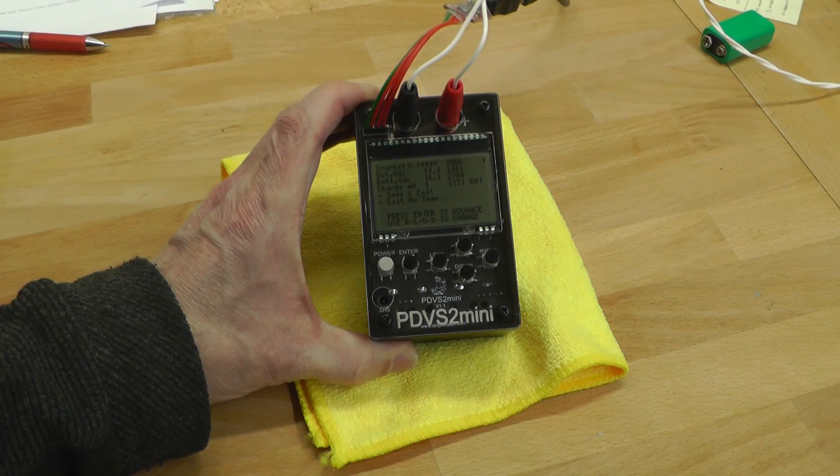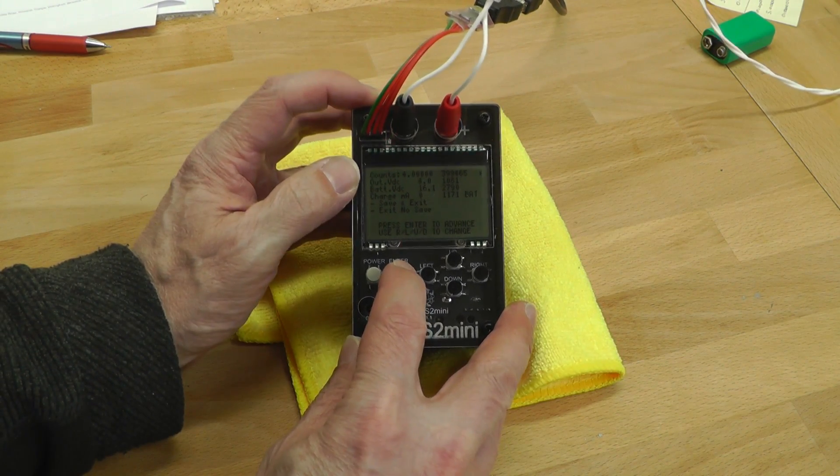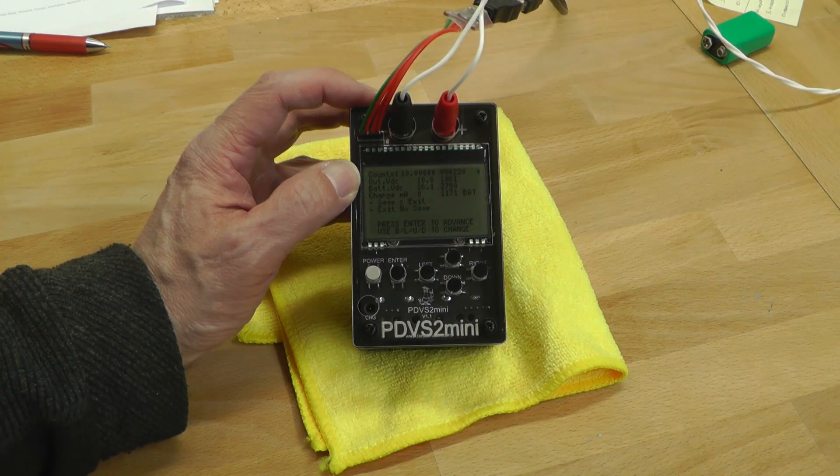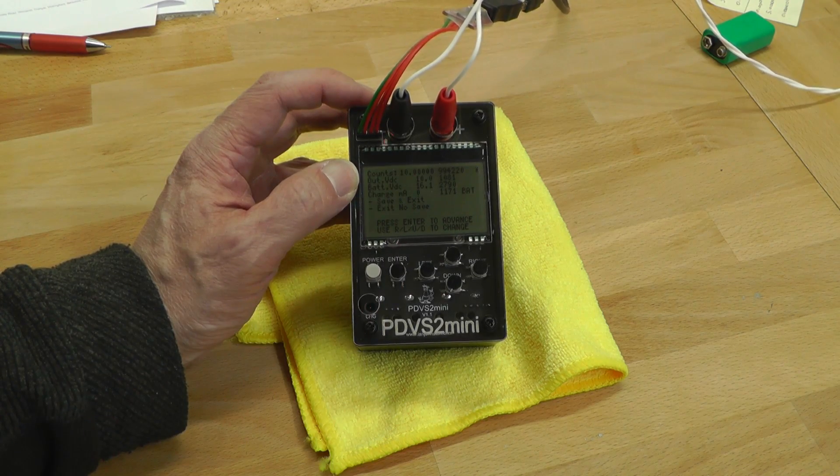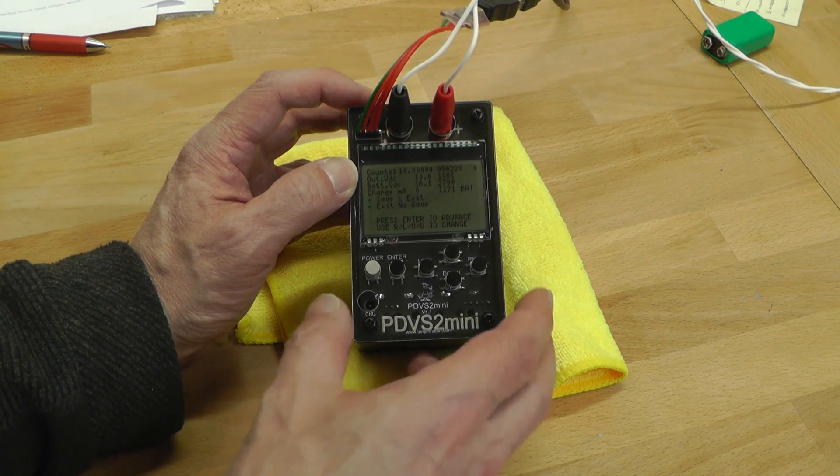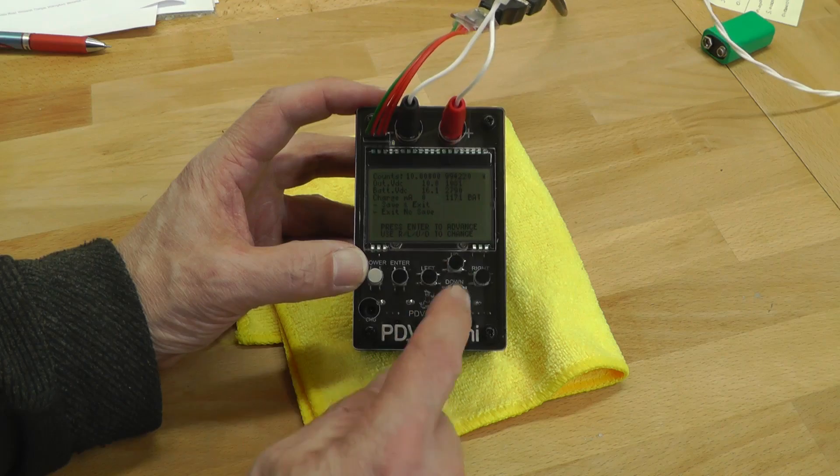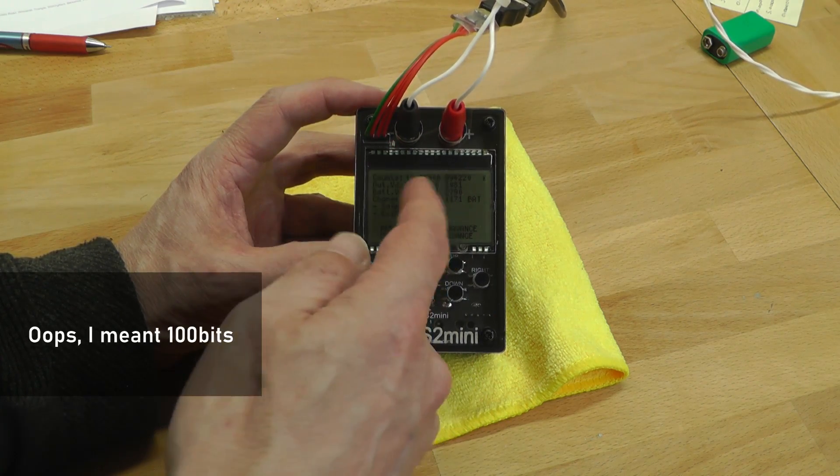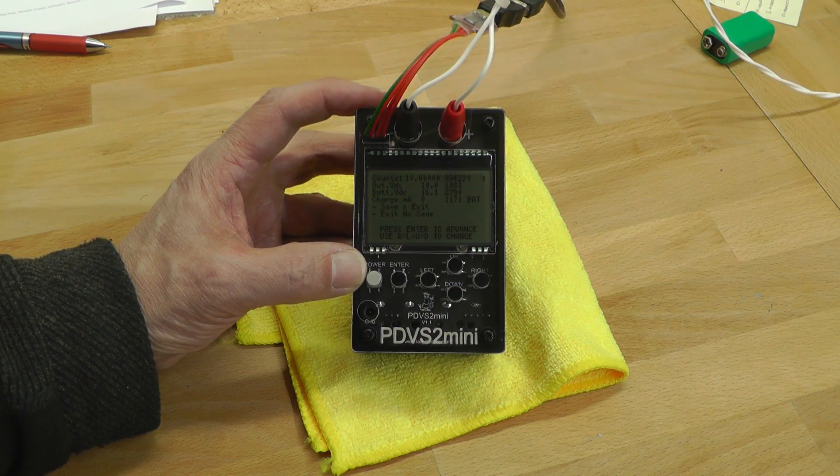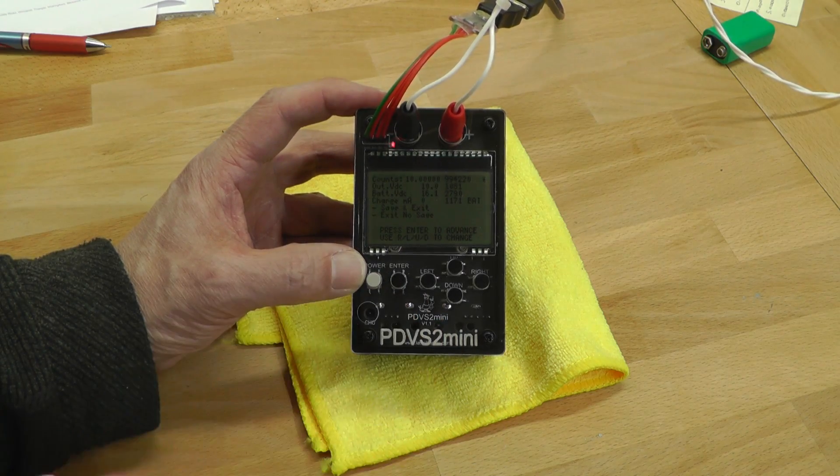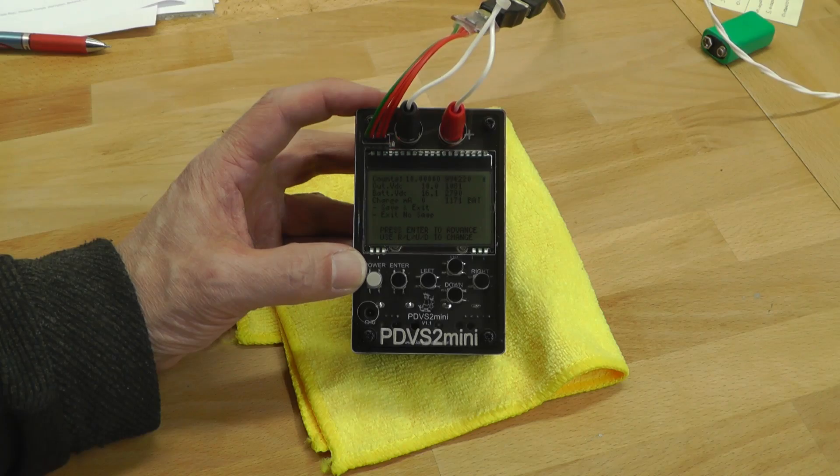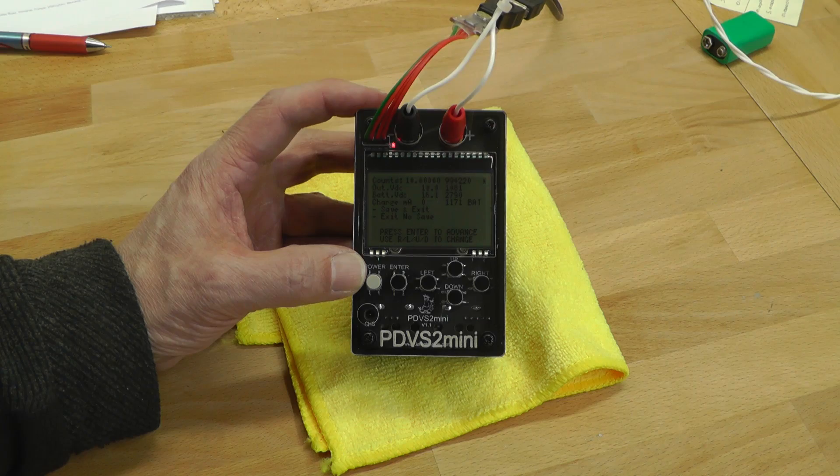So that's this PDV-S2 Mini calibrated. If I then use the enter button to scroll around to the 10 volts there - there we go, there's your 994,220 that you saw on the PC. So now I just need to switch this unit off, the calibration's already been saved, I don't need to manually save it there and that's this one done. So like I said it saves a lot of time because prior to that if I was calibrating 10 volts I'm using the up down buttons to go one bit at a time or the left right to go 10 bits at a time. But when you're 50,000 bits away from your final value that you're looking for, you're pressing these a lot to get to that final value. So this has saved me a lot of time. It takes typically between five and ten minutes to calibrate one of these on this new system using the PC, whereas before it could easily take me 20 minutes to run through all the 11 set points. So it's a big game changer.